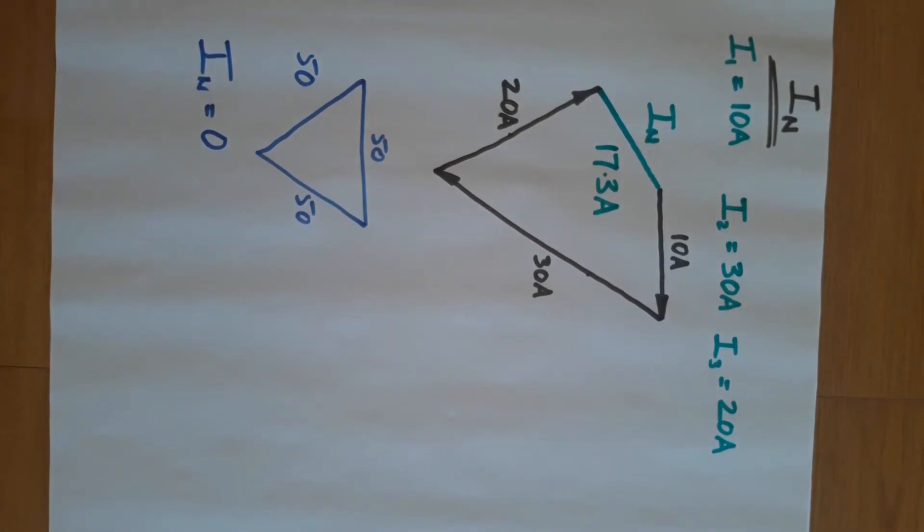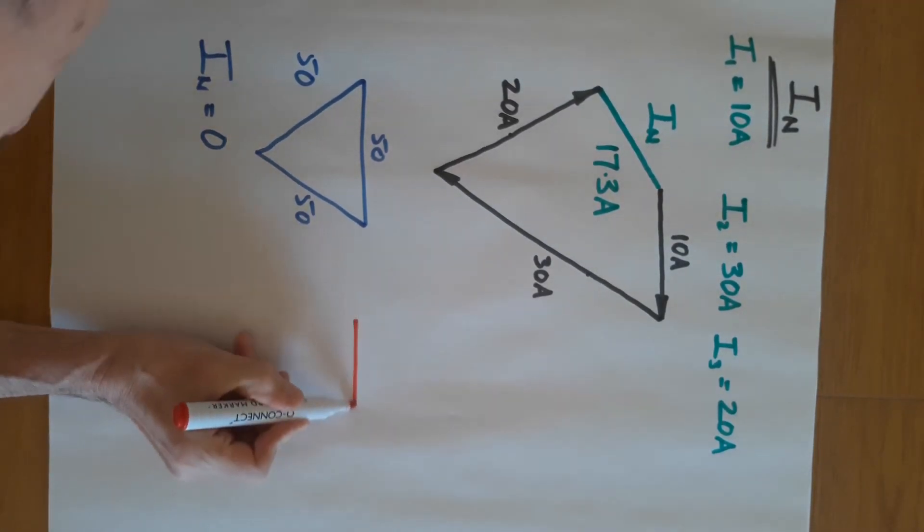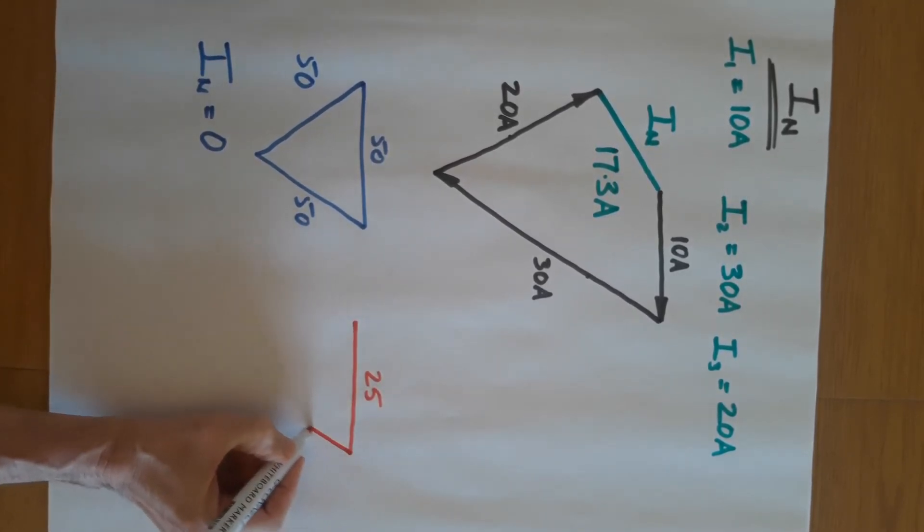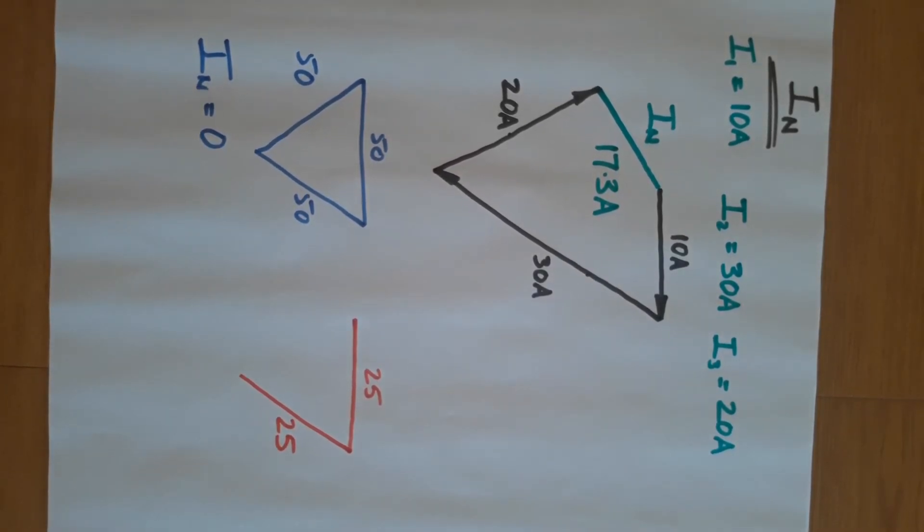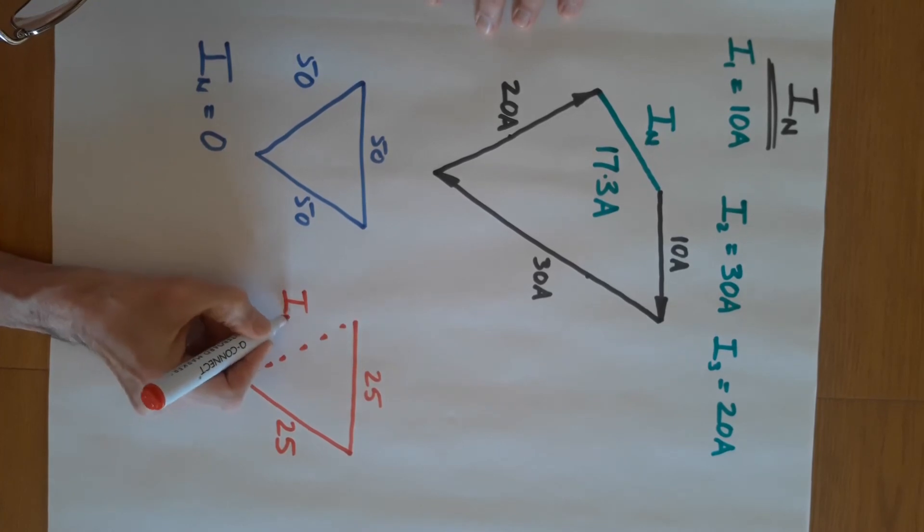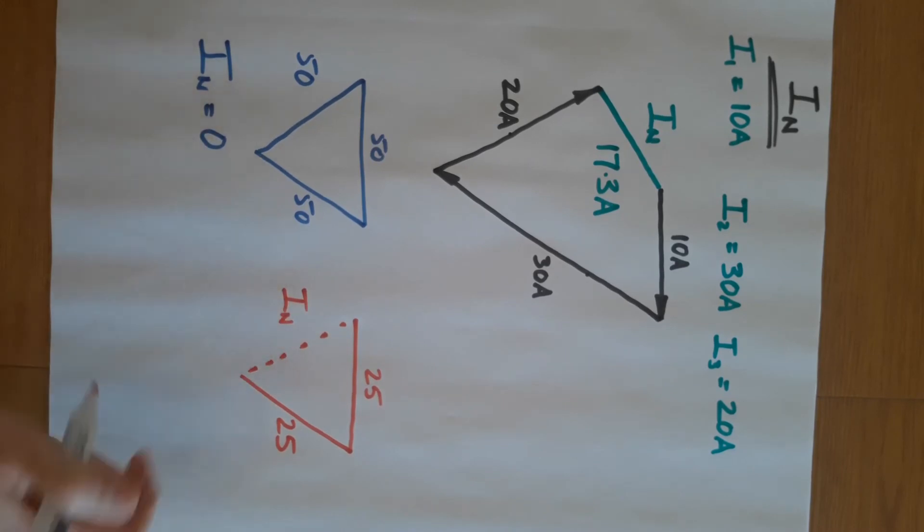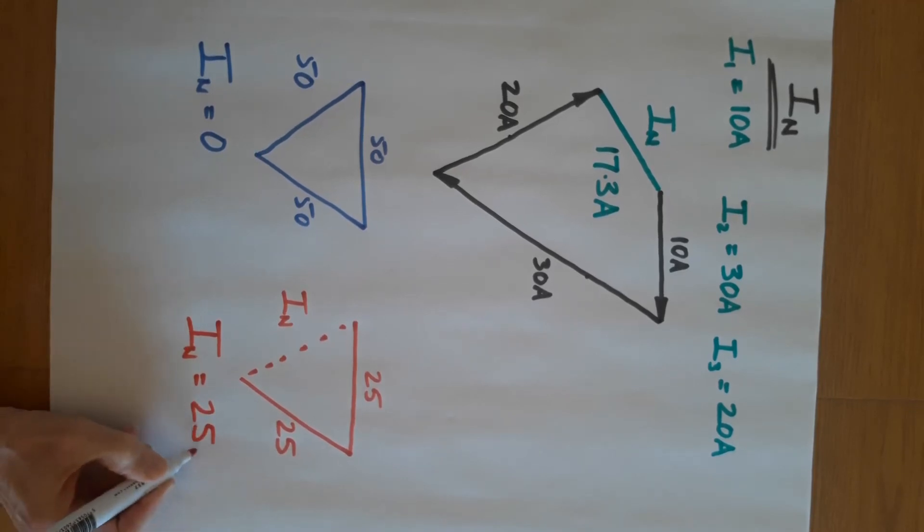One final example. Let's suppose we had 25 amps on the first two phases and nothing on the third phase. So we would draw a line to scale, this is 25, measure around 120 degrees and draw the next one, 25. Those are the two currents in the system, so the neutral current is this one. When you have two equal currents and nothing on a third phase, then the neutral current is the same as one of the other currents.